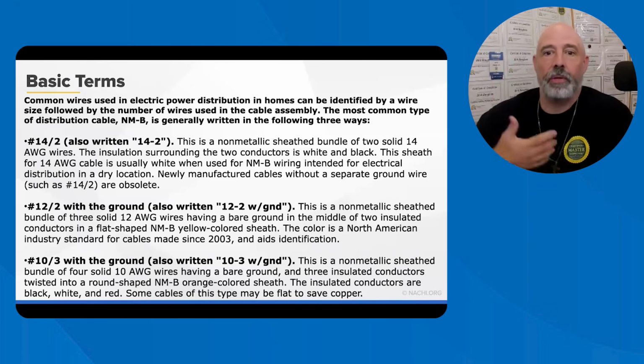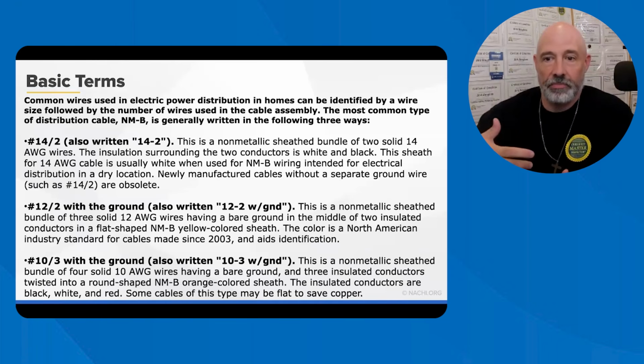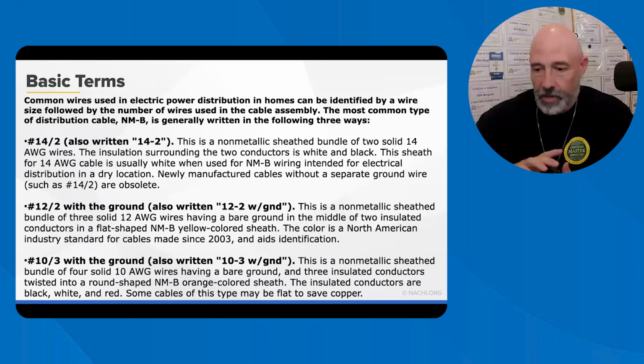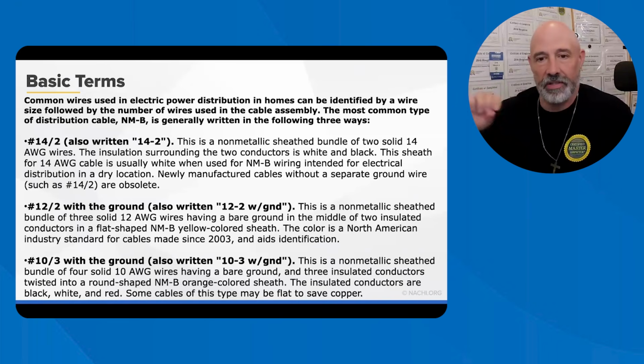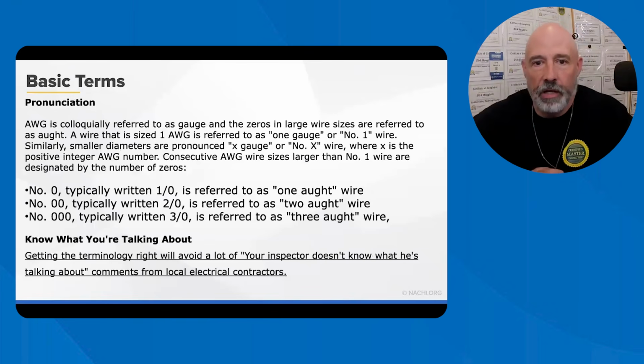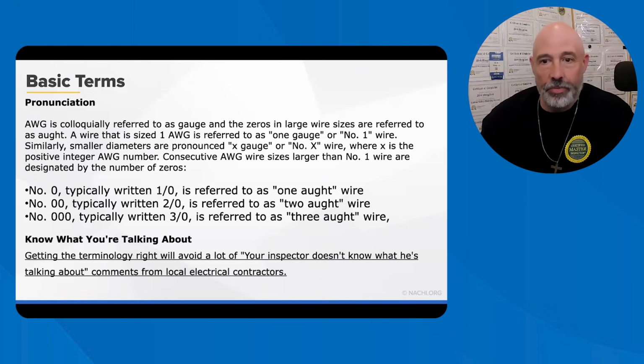As a general rule, the larger the wire number, the smaller the conductor. So think of it like going up: if you look up, it gets thinner. That's how I visualize it in my head. When I'm looking at wire sizes, a lot of times I'll start with the smallest one, which is the 14 gauge, and then I can visualize the size from there when I'm doing inspections. In the electrical industry, AWG is most commonly referred to as gauge wire, while larger conductor sizes use the term aught. So 1 AWG is 1 gauge, and then you've got 1/0, or the 2/0, or whatever it is. Using the correct terminology helps you communicate a little bit more with the electrician if or when you ever talk to them. A lot of times I'll do the re-inspects and talk to the electrician right there, and it's kind of fun.